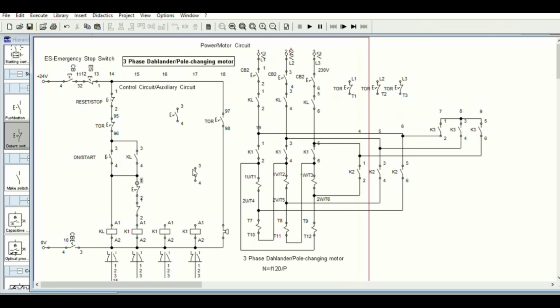Now, there are several ways to control this one. Like to close this one first, open or close transition using resistors, and turn on this one first. Or you can turn them on together, which is according to the size of the motor. If the motor is just small, you can just open transition. If it is so big, that will surely impact the mechanical load of the motor. I mean, the mechanical load will impact the restarting or the mechanical jerking of the motor.